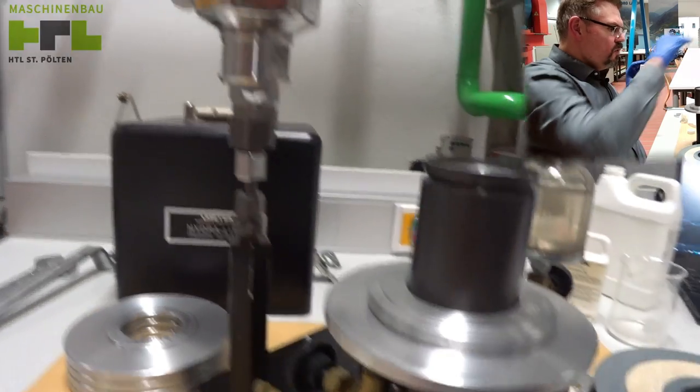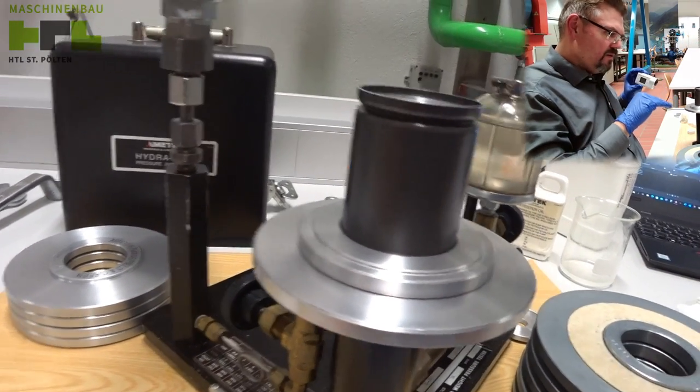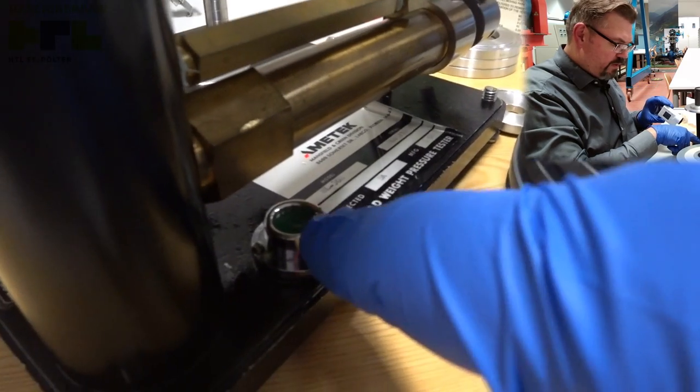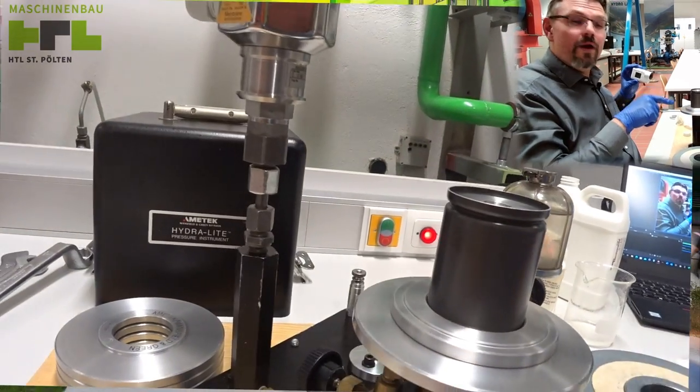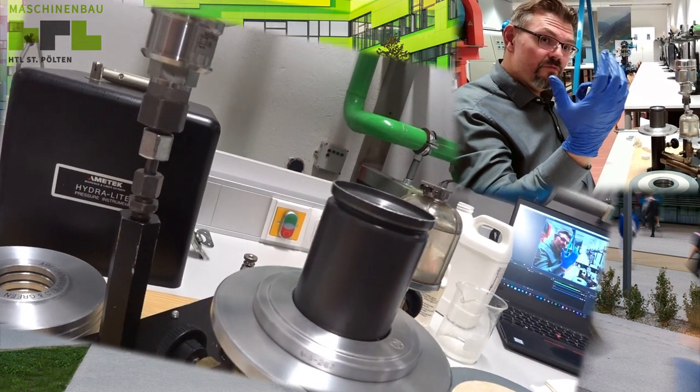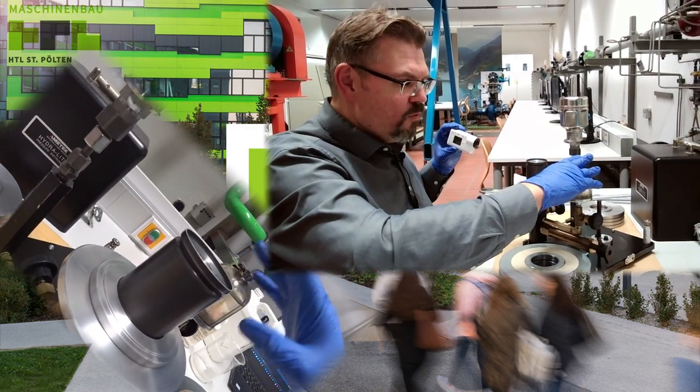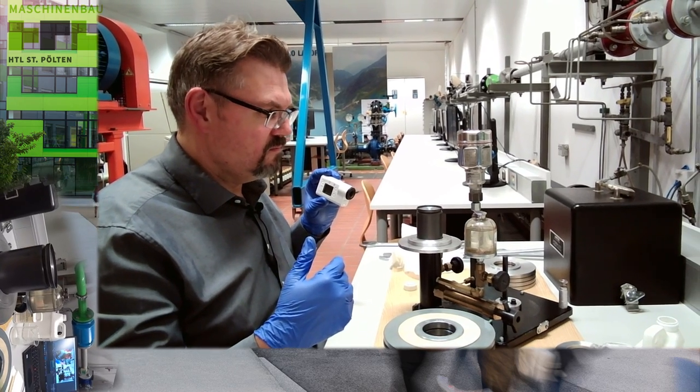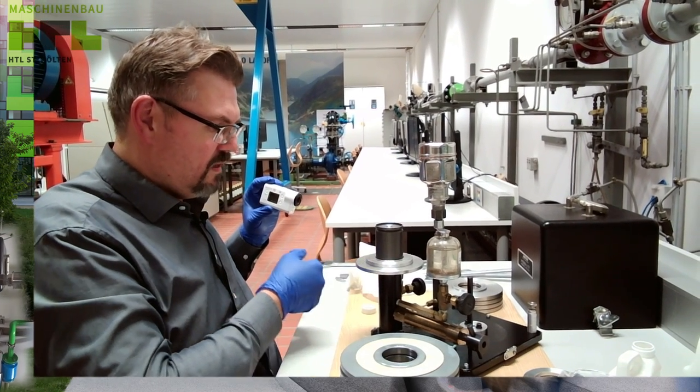And now I have 1.2 bars. And this is how you can check your sensor with a highly accurate measurement device. However, everything must fit together. This must be leveled. So we have here something which will help us. The correct weight must be on, you only have to touch them with gloves so that you're not leaving any fingerprints, so that the measurement is not disturbed too much. And we have to use a special liquid where the viscosity and everything is exactly right.